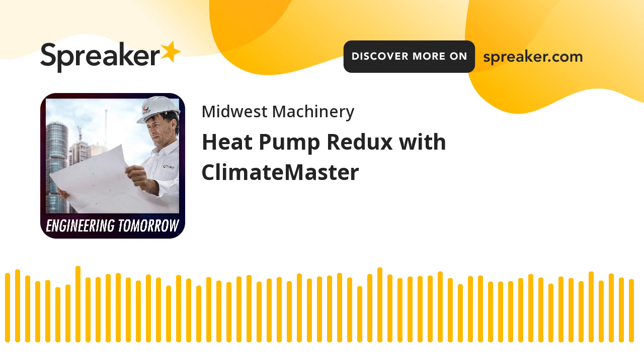And last but not least, what makes a heat pump is the reversing valve. This device allows the two heat exchangers to act as an evaporator or a condenser, allowing the unit to provide either cooling or heating to the space. During the cooling mode, heat is extracted from the air by evaporating the refrigerant in the refrigerant to air heat exchanger. Hot gas from the compressor enters the refrigerant to water heat exchanger. In the cooling mode, the refrigerant to water heat exchanger acts as the condenser.